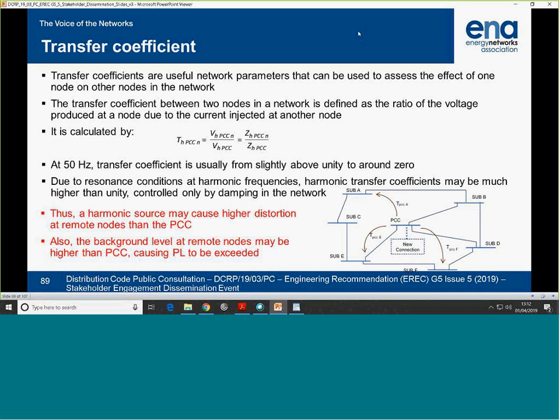To make it clear, when you connect a generator at one point, you want to see what sort of voltage it produces at other nodes: the voltage drop or voltage rise you get at the other substations. It's the same. The only difference is that at 50 Hertz, usually connecting a load or a connection, your coefficient is around 1. Or if you consider a fault, it can be very low, causing voltage at other nodes to go to 0 or close to 0. For harmonics, because of resonances and interaction between the line capacitance and inductances, transformer inductances, and all of that, transfer coefficients may be much higher than unity.